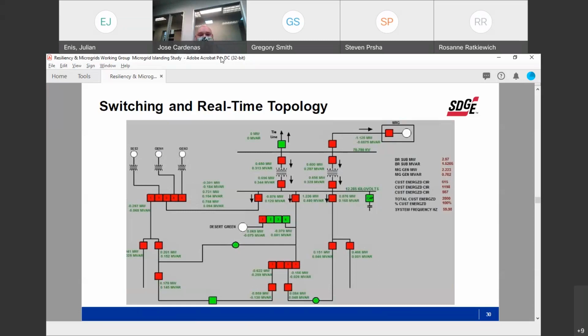In a black start situation, all these breakers you see red down here will be green, and we'll be doing load steps. The microgrid will create the voltage and frequency, and then it'll start doing its restoration steps. Like we talked about with cold load pickup, you first energize that first section of the line, and you're going to pick up the inrush from energizing the line. All the air conditioning, refrigerators, all those loads are going to hit the system at once, and then it'll taper off and get to a steady state condition, right?